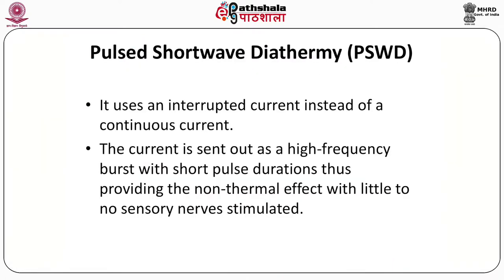The second mode of shortwave diathermy is pulsed shortwave diathermy (PSWD), which uses interrupted current instead of continuous current. The interrupted current is sent out as a high-frequency burst with short pulse duration, providing non-thermal effects with little to no sensory nerve stimulation.